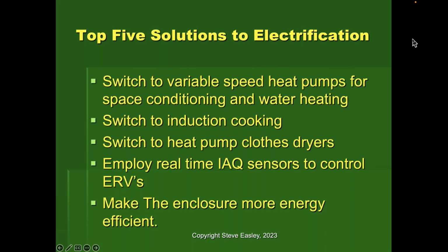Traditionally, we run our ventilation systems according to ASHRAE 62.2, which is a standard that says, based on the square footage of your house or however many people are living there, that you have to provide a set amount of ventilation. Using real-time IAQ sensors that can actually monitor indoor air quality and control those ERVs based on your true indoor air quality is definitely a step in the right direction, instead of a formula that just runs the fan so many minutes out of every hour or so many hours out of every day.